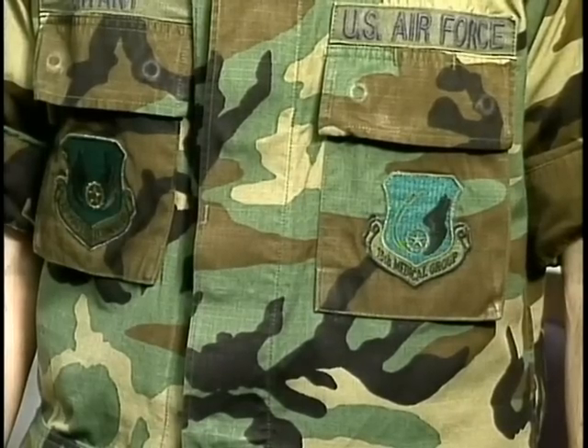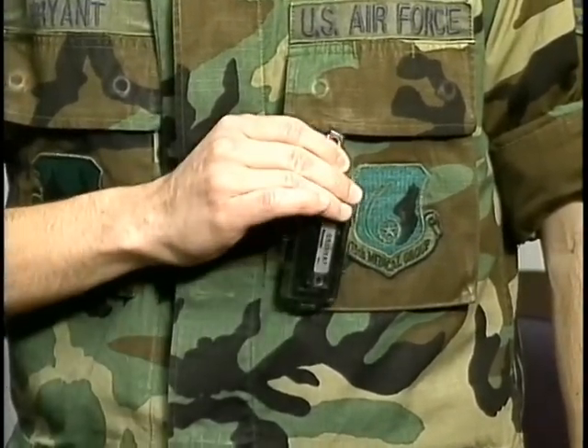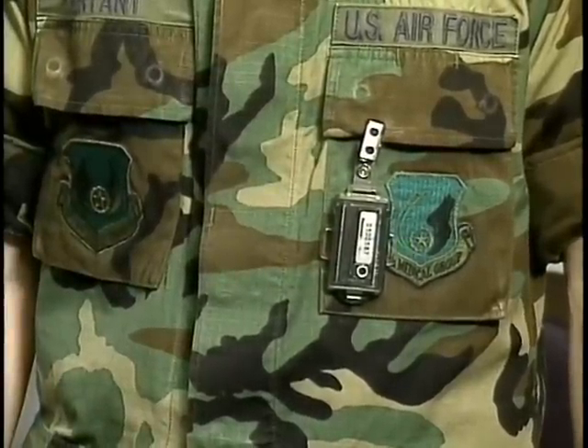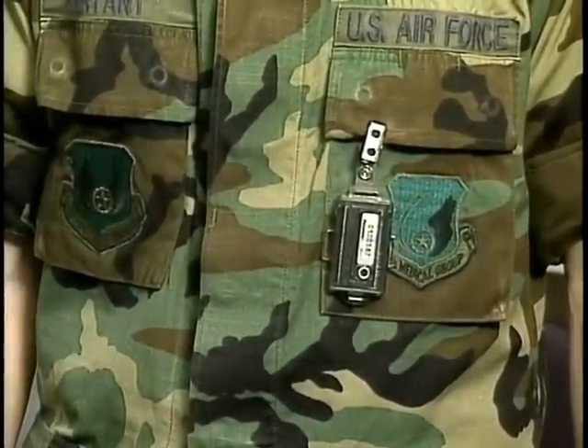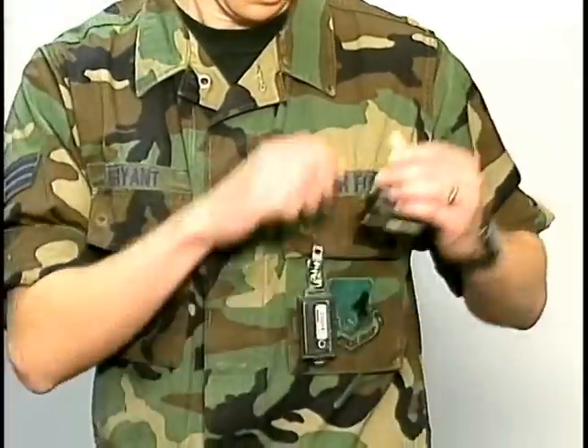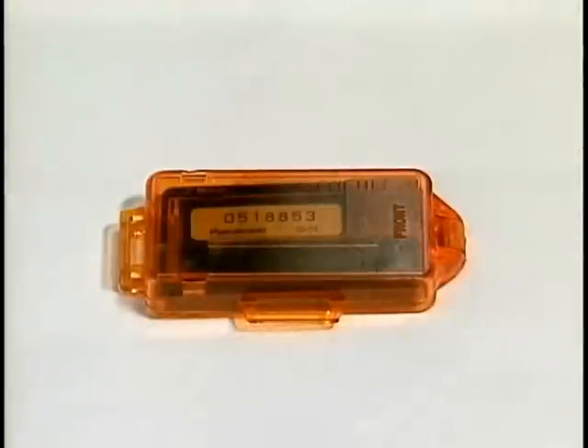The whole body dosimeter must be clipped on the front of the body, below the shoulders and above the hips, and is always worn underneath any personal protective equipment in use, especially lead aprons. The collar dosimeter is worn on the collar and is required to determine exposures to the head and eyes when a lead apron covers the whole body dosimeter.